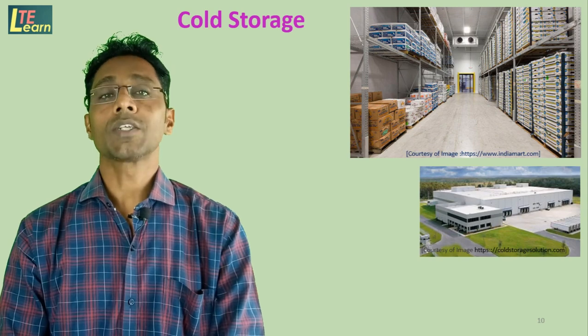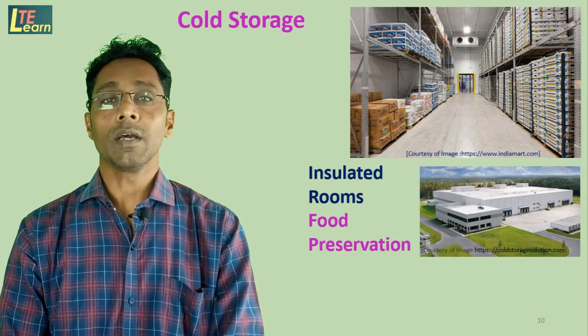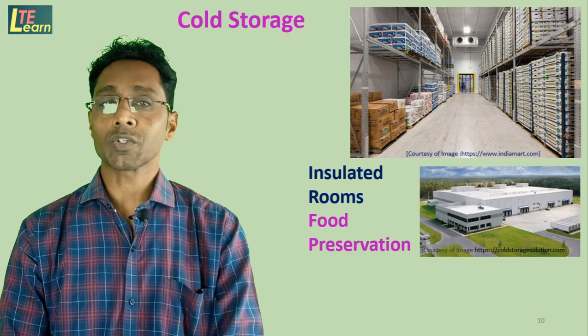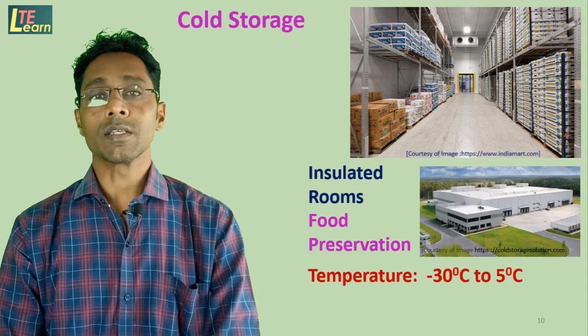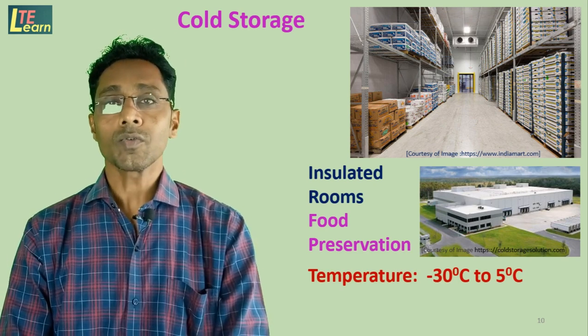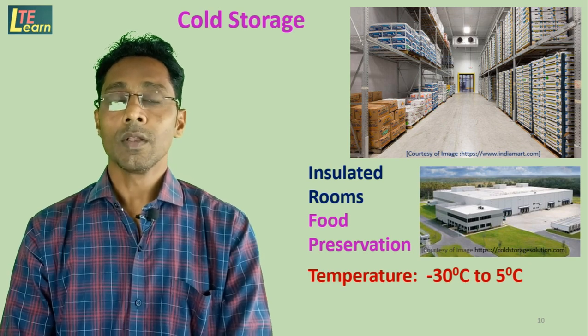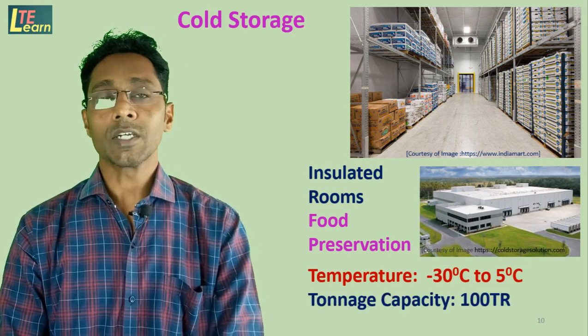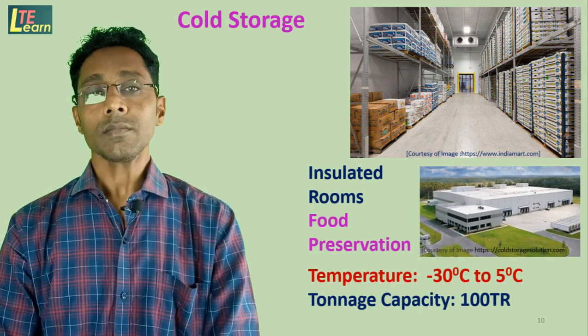Cold storage: These are insulated rooms used for food preservation, where food products are stored for short-term or long-term periods. The temperature availability is minus 30 degrees Celsius to 5 degrees Celsius depending on the type of food. Tonnage capacity for cold storage is about 100 TR and the refrigerant used is ammonia.